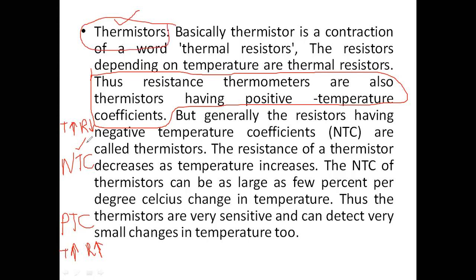Thermistors are examples of negative temperature coefficient devices. There are other devices which also come under resistive transducers, but their resistance increases with increasing temperature. Those are called RTDs. RTDs are examples of resistive transducers which work on the principle of positive temperature coefficient, meaning if temperature increases, resistance also increases. So these two points are clubbed here - resistance thermometers are also thermistors.